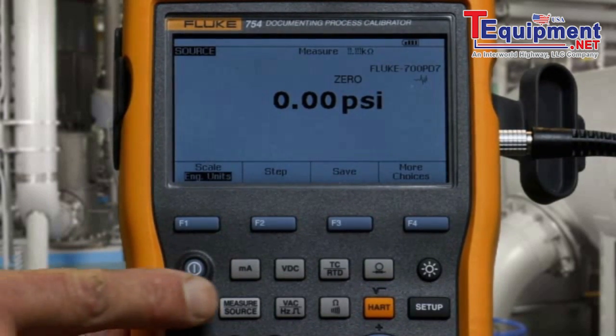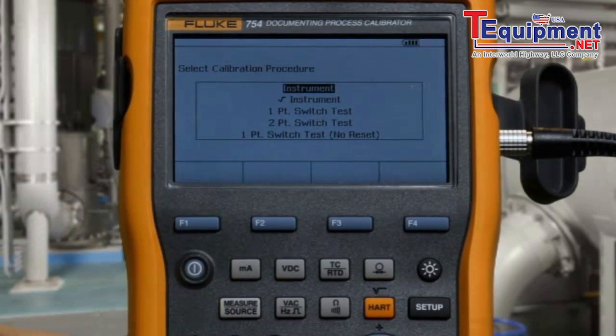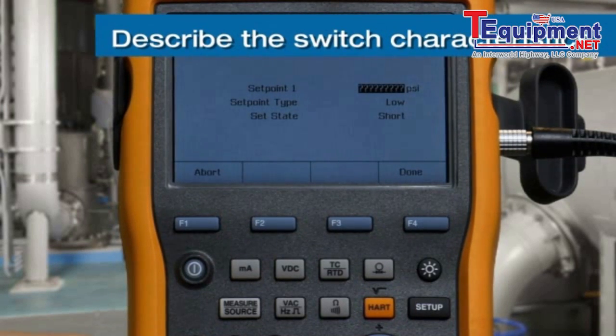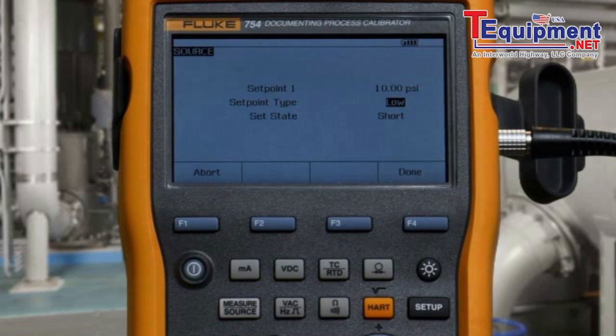To perform the test, we need to get to the split screen and select As Found for a one-point switch test. To define the test, we press Enter on Setpoint. We're expecting a setpoint of 10 PSI, and the setpoint type is low — so below 10 PSI, we're looking for shorted contacts.